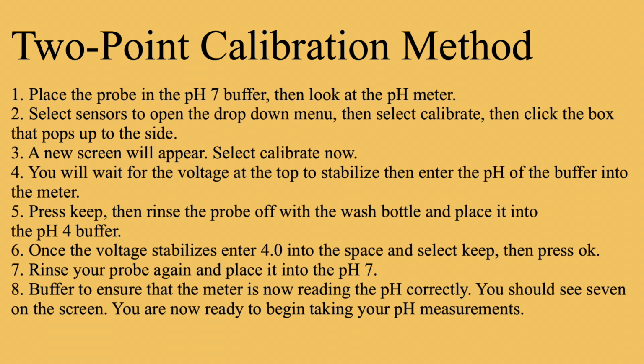Rinse your probe again and place it into the pH 7 buffer to ensure that the meter is now reading the pH correctly. You should see 7 on the screen and you're ready to take pH measurements.